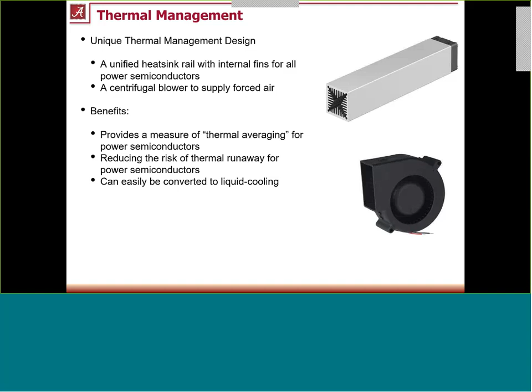Some benefits of this design: it provides a measure of thermal averaging, so if some semiconductors are hotter than others, we get some thermal balancing, which helps mitigate the risk of thermal runaway. Another advantage is that we can easily convert this to liquid cooling simply by sealing the ends of the tube and hooking up a chiller instead of forced air.